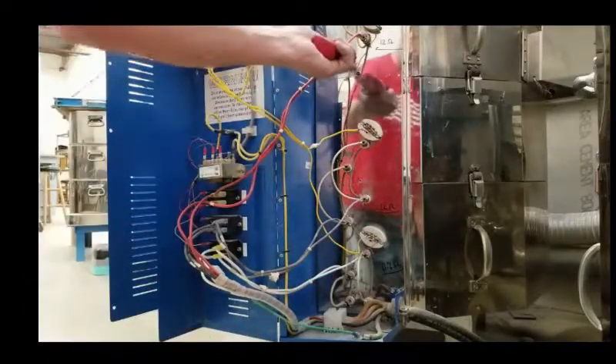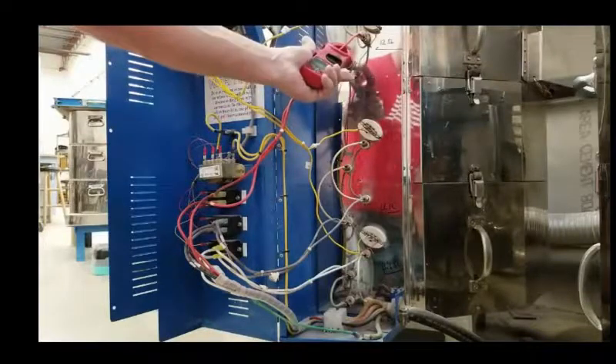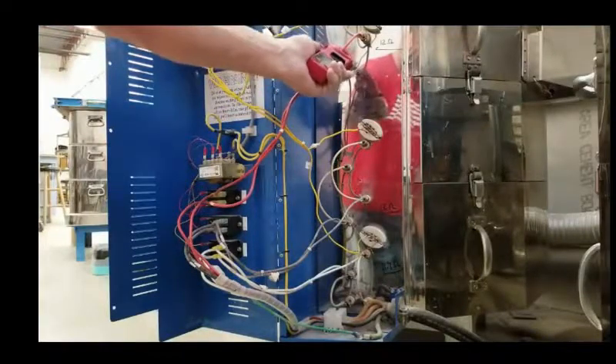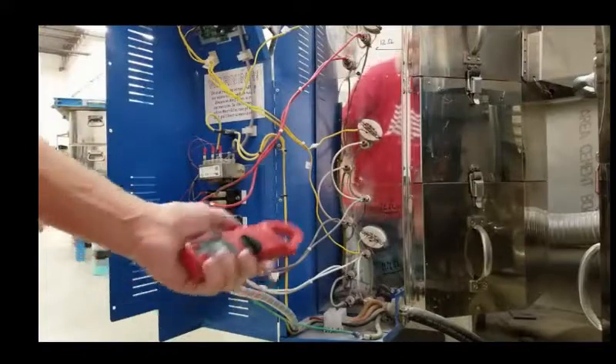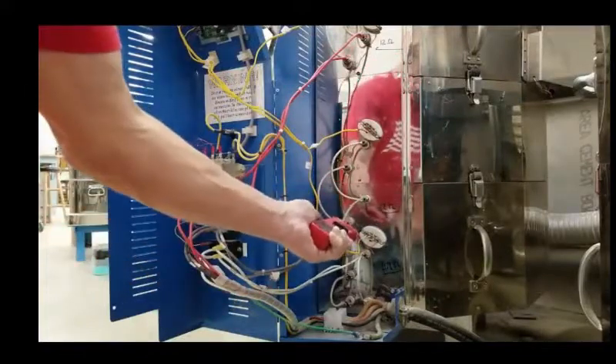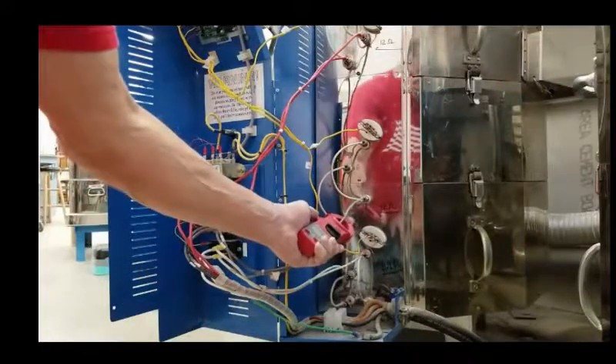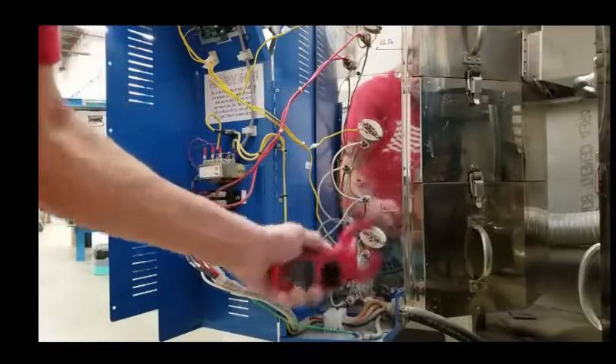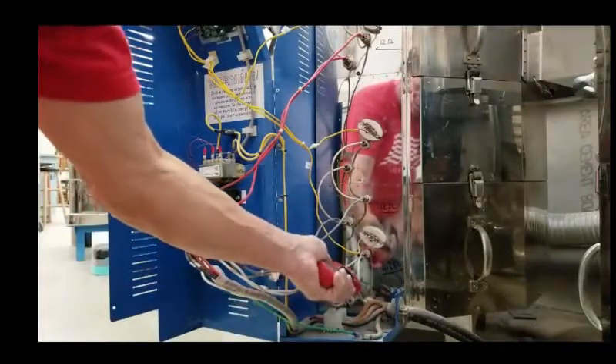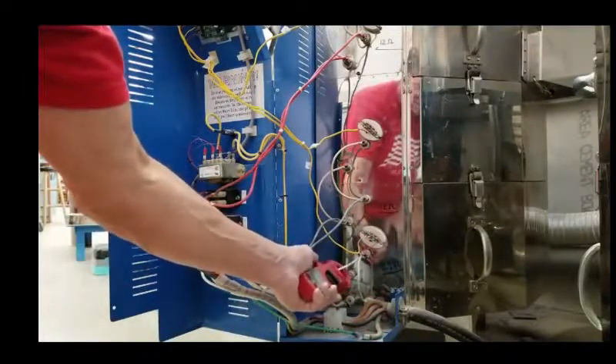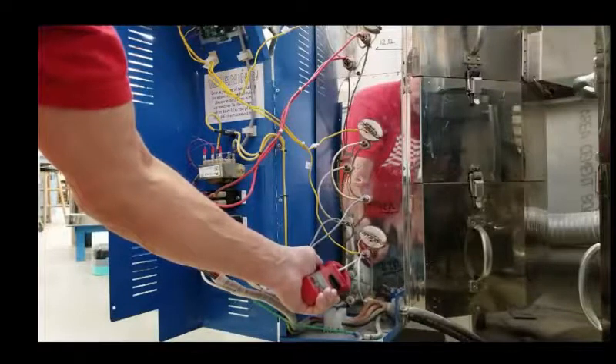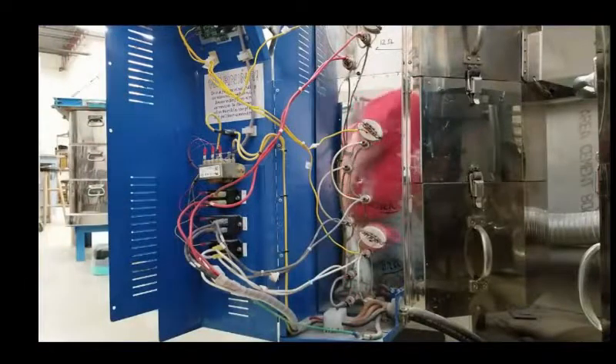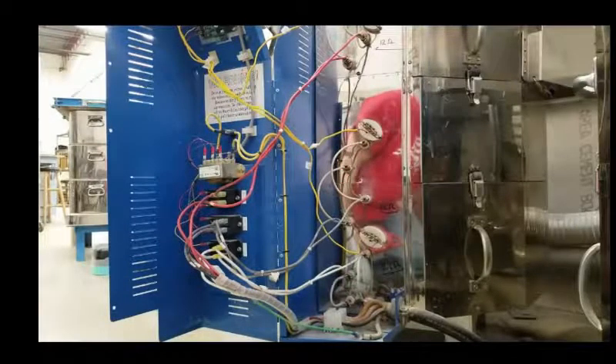If I look at the top two elements, I get 16.1 amps. If I look at the middle elements, I get 16.4 amps. And the bottom element, I get just 17 amps. I like all those numbers—they're within range for this machine, nothing out of the ordinary. I'd be pretty happy with that.